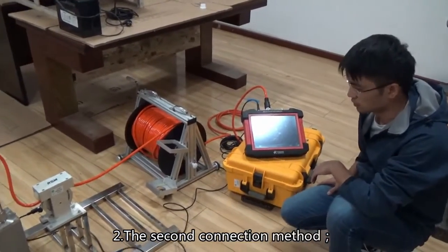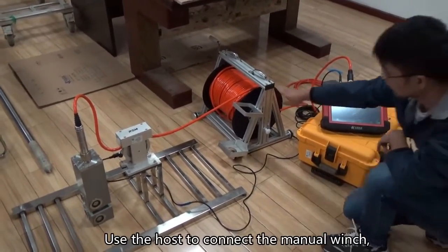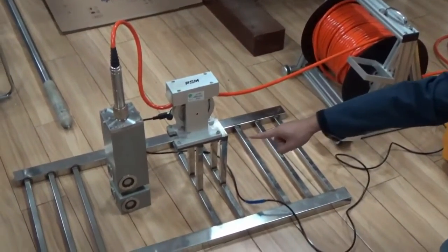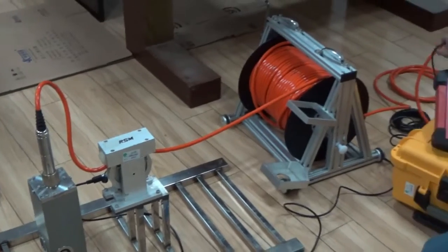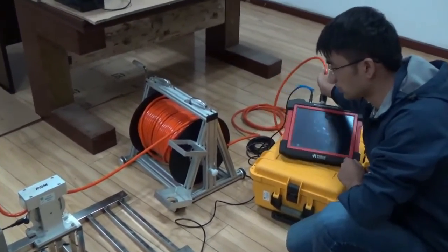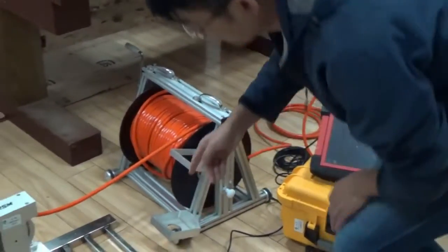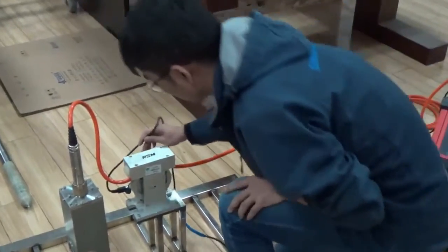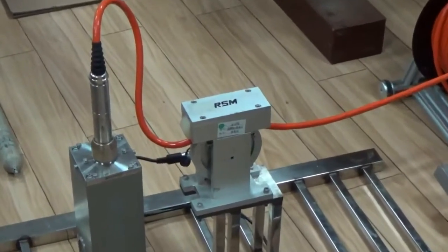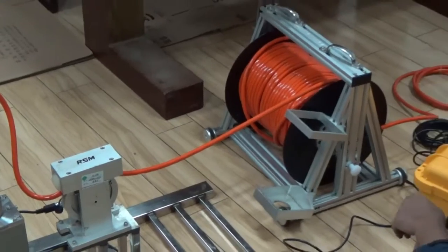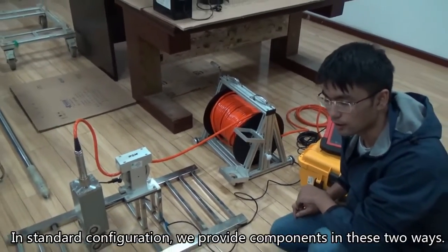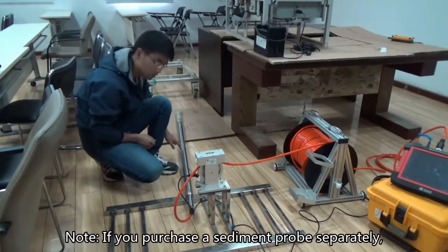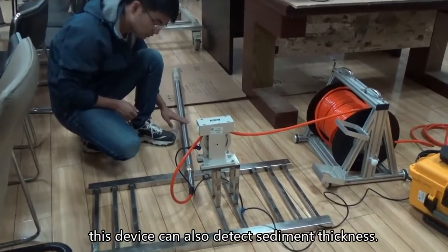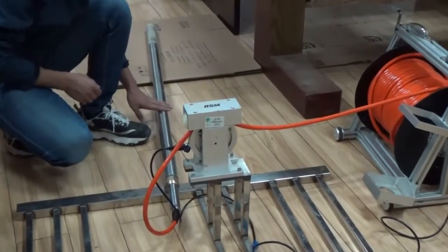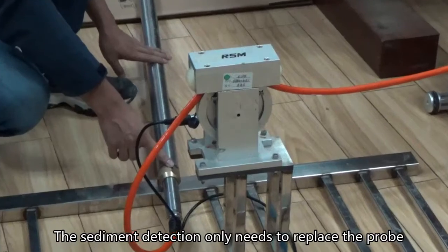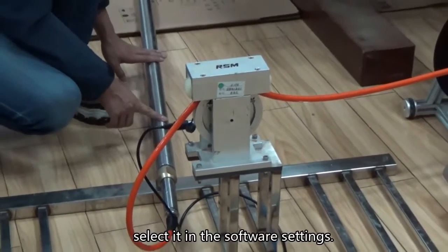The second connection method: use the host to connect the manual winch. And then connect the depth counter cable. In standard configuration, we provide components in these two ways. Note if you purchase a sediment probe separately, this device can also detect sediment thickness. The sediment detection only needs to replace the probe and select it in the software settings.